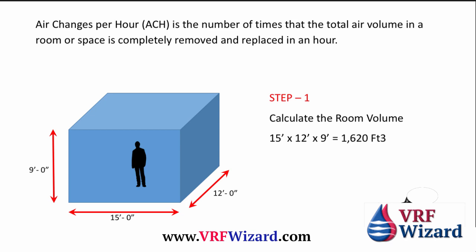Step one: calculate the volume of the room. In this case, we have a 15 by 12 foot room with a 9 foot high ceiling. You want to go to the ceiling and not to the deck or the area below — only the space from which you're going to pull out the air. In this case, that works out to be 1620 cubic feet.